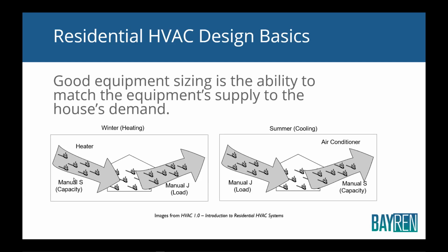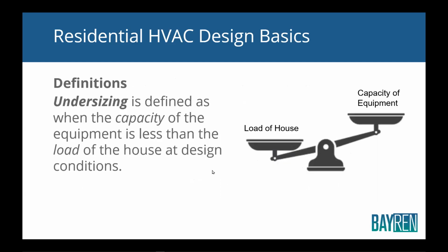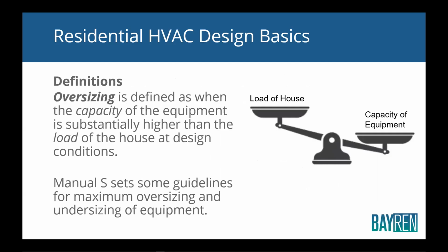Furnaces are just kind of dumb beasts. They'll tell you what's the output of a furnace, and that's pretty much it. Unless you go up to really, really high altitudes, that drops a little bit. But heat pumps, on the other hand, are much more complicated. Again, that is why good design is so important for heat pumps. So undersizing is defined when the capacity of the equipment is much less than the load of the house, or just substantially less than the load of the house. It's undersized. So on a design day, it may not keep up, okay? And then oversizing equipment is when the capacity of the equipment is much higher than the load of the house. And you've got all this excess capacity that you've paid for, but you probably will never need, okay?